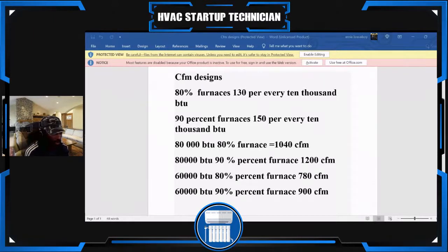You also want to look at your ductwork. You want to make sure the ductwork you use is appropriate for the furnace. If you look on Amazon or any of those sites, you can get a duct slide rule, and it will also tell you how much CFM it is rated for.